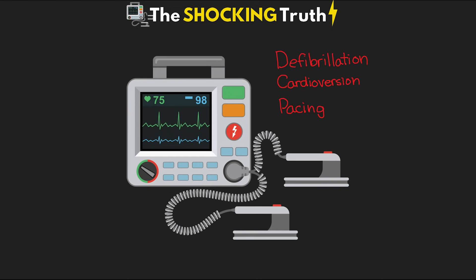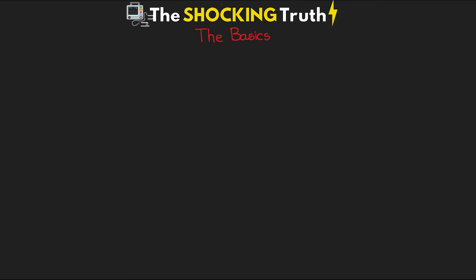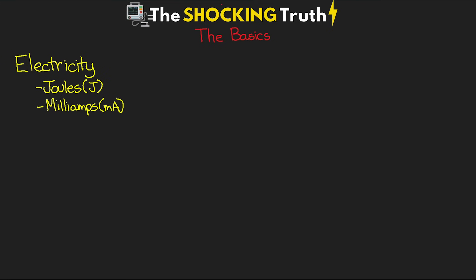Before we talk about each of these modes, I want to cover some basic information about electricity, which is what really makes all the magic happen. You'll come across two different measures of electricity on the defibrillator. The first is joules — essentially a measure of amps times voltage times some period of time — and the other is milliamps, which is just the current. It's important to know you'll see these different measures depending on which mode you're in.